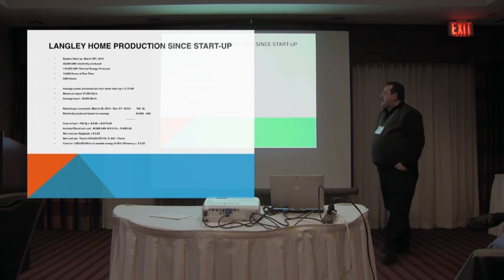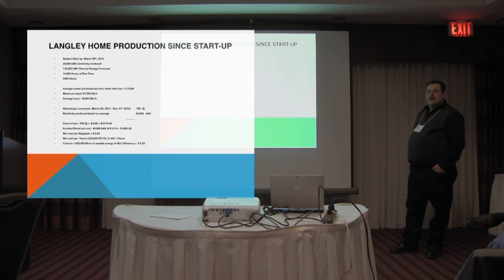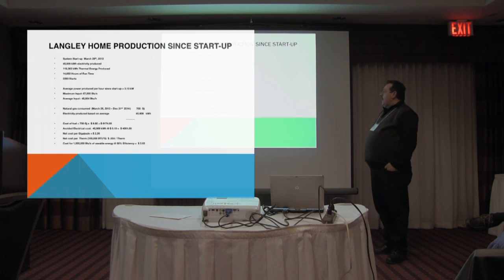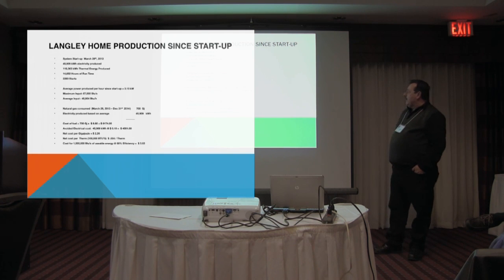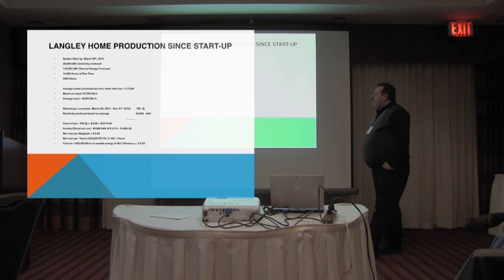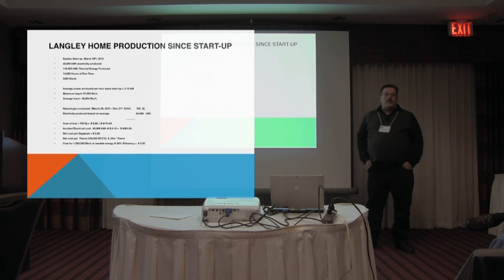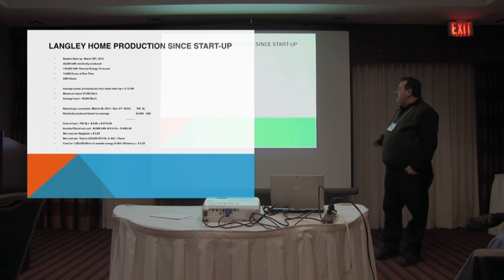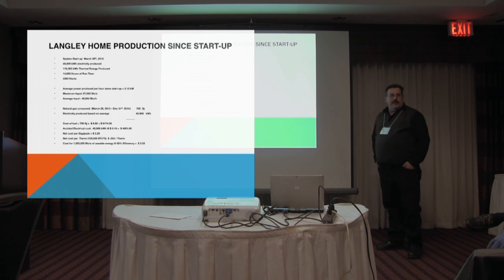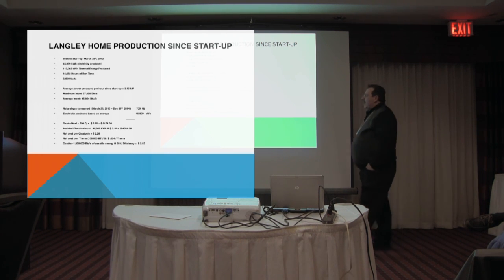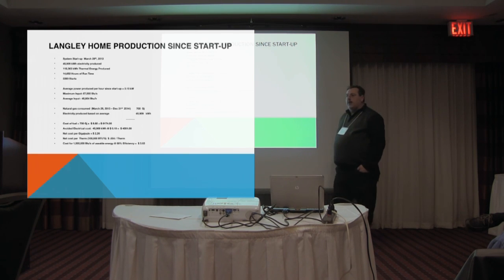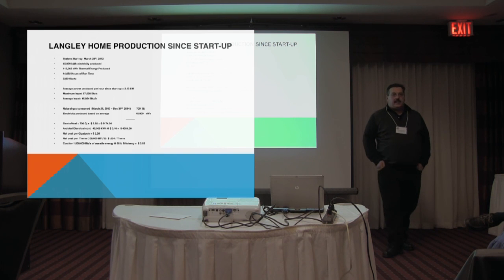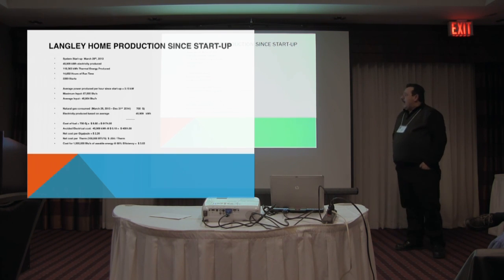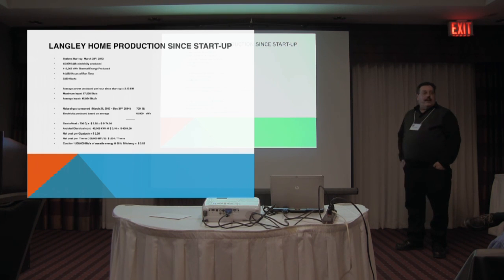The natural gas that was consumed from March 28th to December 31st, 2014 was 700 gigajoules. And the electricity produced, based on the average, is about 45,909 kilowatt hours. At that time, natural gas was about $8.82 a gigajoule, which meant that the cost for that fuel would have been about $6,174. The avoided electrical cost, we had 45,909 kilowatt hours, where the average cost at that time would have been around 10 cents a kilowatt hour. So it's produced as a byproduct, really, $4,591 worth of electricity.